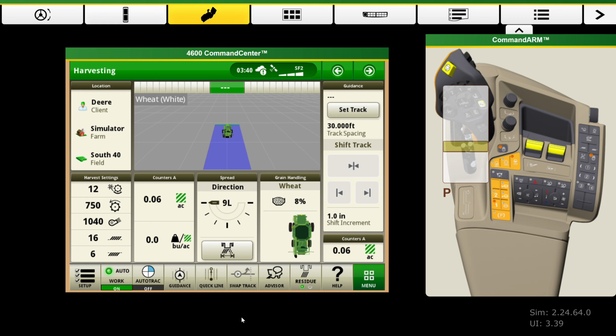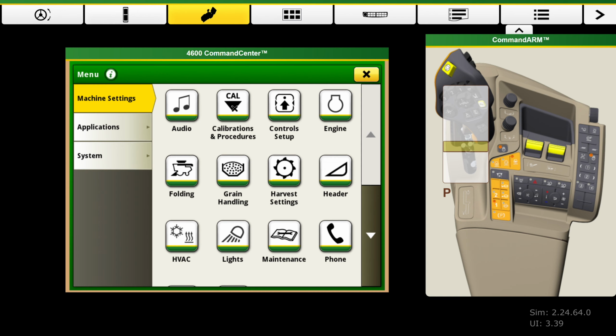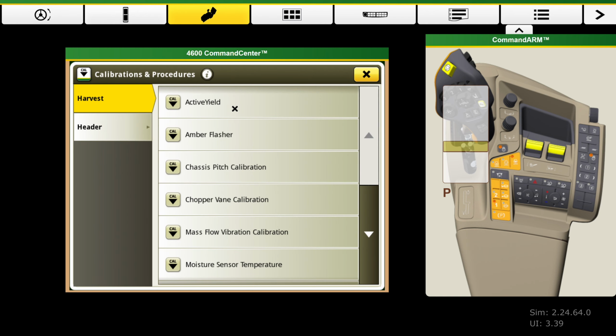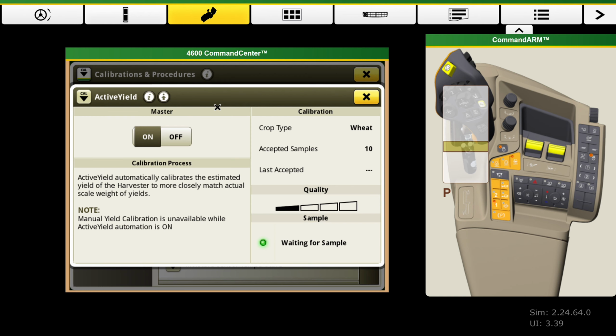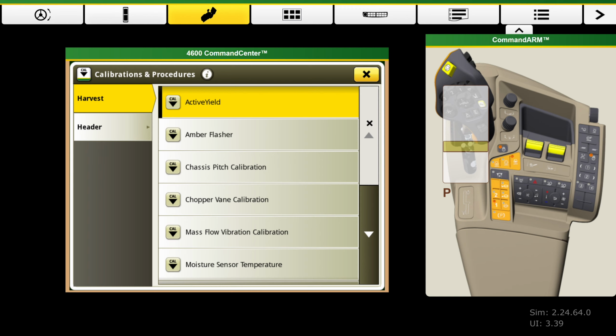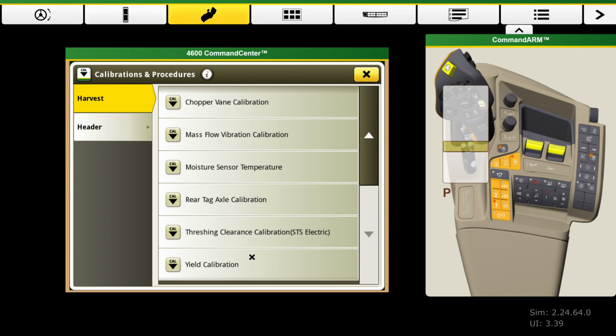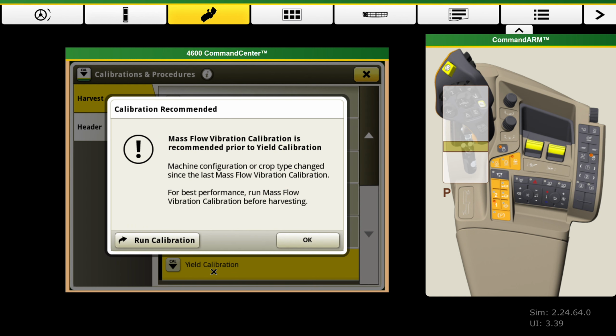To calibrate an S700 manually, we will first need to shut active yield off. Select the menu button, go to Calibrations and Procedures, select active yield, and turn active yield off. Scroll to the bottom of Calibrations and Procedures and select Yield Calibration.